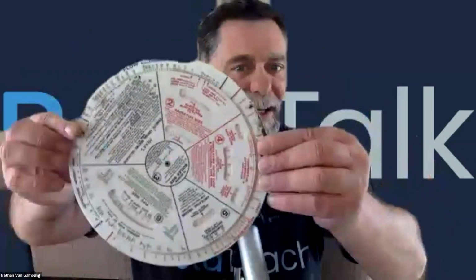So you'll find, back when the first heating systems were designed, I don't know if you can see this, but this is the old Mears calculator we used to use to size pipework and radiators. They were single panel radiators. As long as they were clean, they did corrode and clog up, but a single panel radiator was heating homes in the 60s, 50s, 70s, designed to work around the UK average of minus 3. So we don't usually have single panel radiators now.